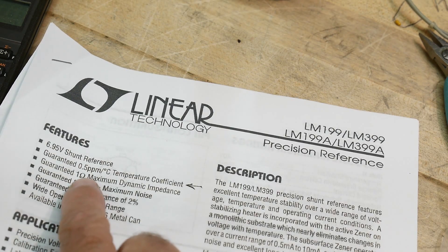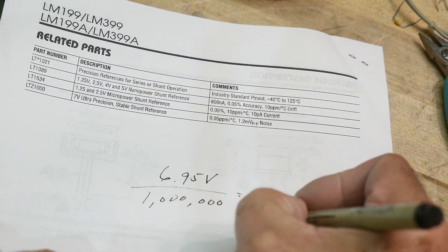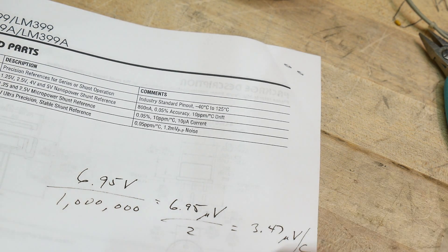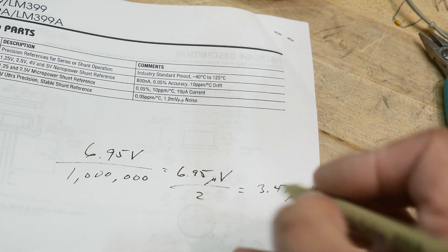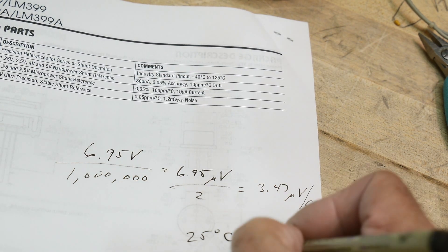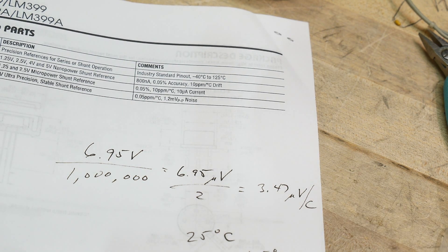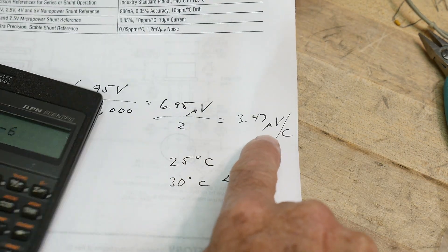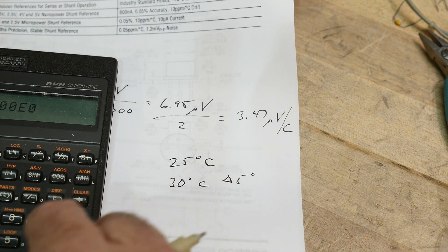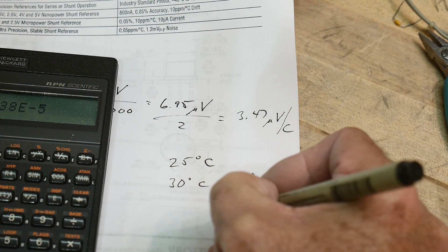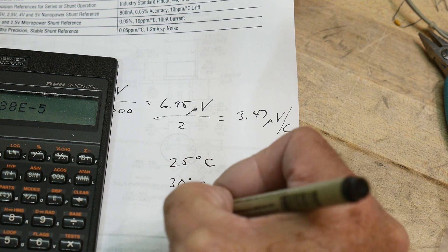But the datasheet says 0.5 ppm, so that's one half, so we get to divide this by two. It's 3.47 microvolts per degree C. That means if you calibrate your instrument at 25 degrees C and you use it at 30 degrees C, you have a five degree delta.